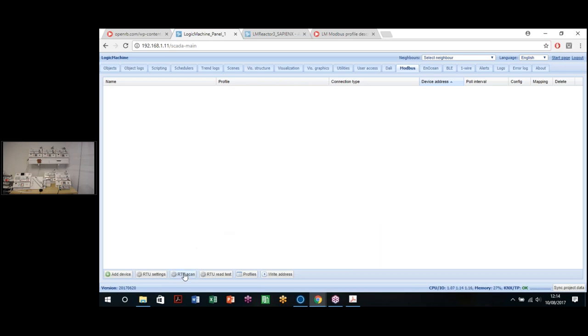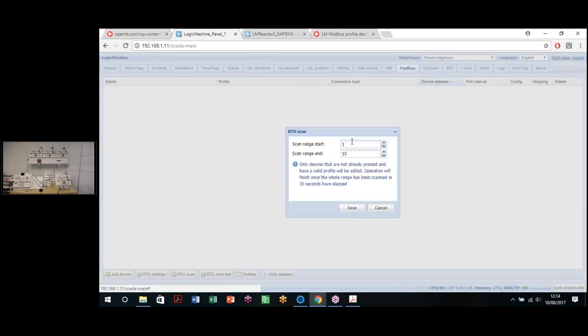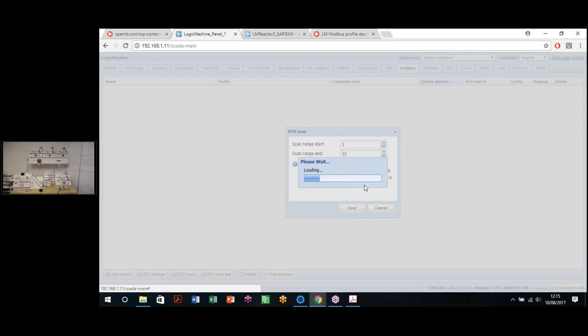And we click on RTU scan. With this tool, we can search all the devices connected to the Modbus bus. In this case, I'm going to search from 1 to 10 because I only have one device. We can search from 1 to 247, which is the top of the Modbus addressing. Notice that we only have 30 seconds for this search, so it's recommended to search in chunks, let's say from 1 to 10, from 10 to 20, and so on. In this case, we are going to search, and it should show us the device that we have connected.